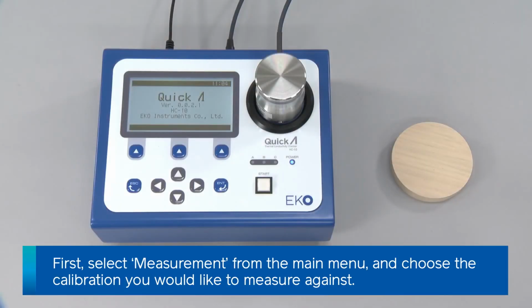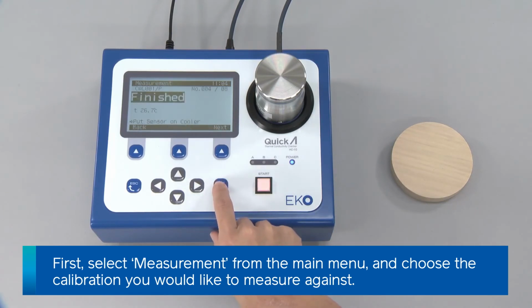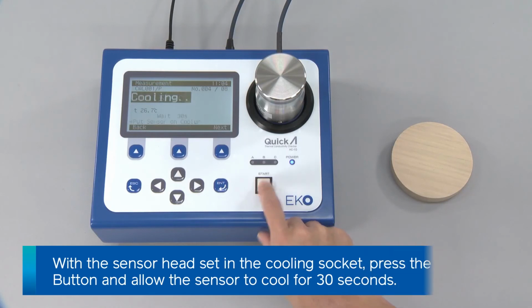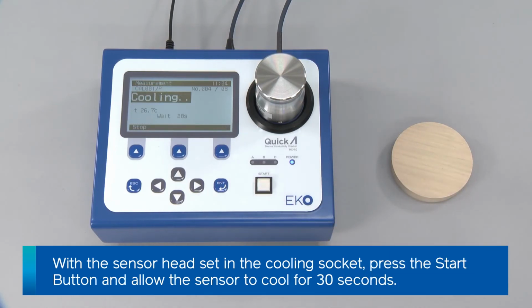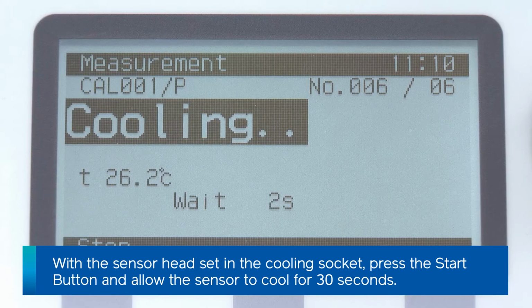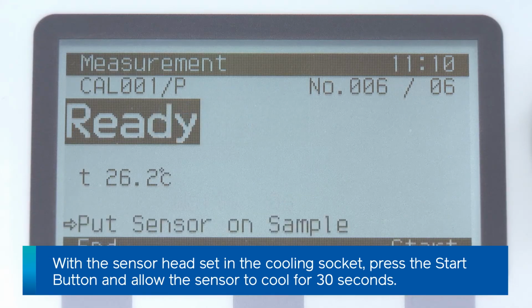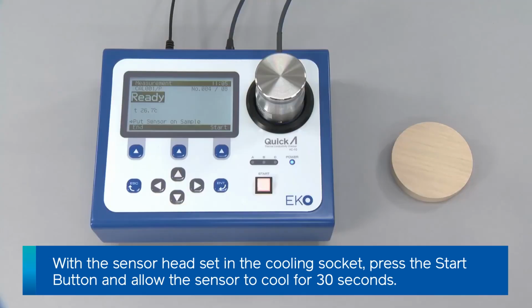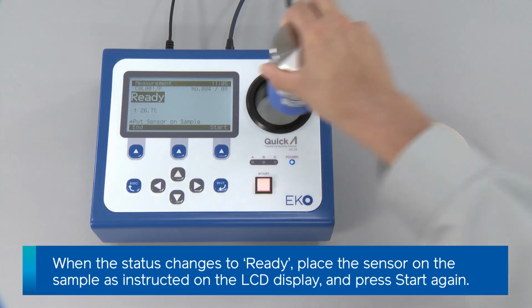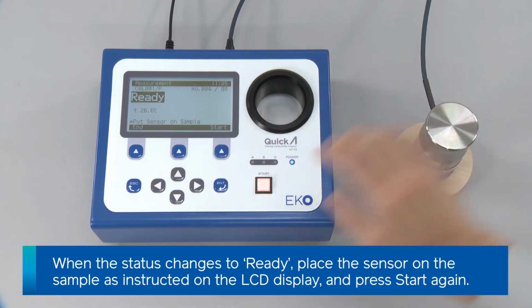So, we've learned how to calibrate the HC-10, but how do we actually measure samples? To start measuring using the calibration file you made, select Measurement from the main menu and select the calibration file related to the samples you want to measure. This is the file you created during the calibration step. Then, with the sensor head in the cooling socket, press Start to begin the cooling process, just as we did when measuring those calibration samples. When the status changes to ready, place the sensor head on the sample and press Start again.